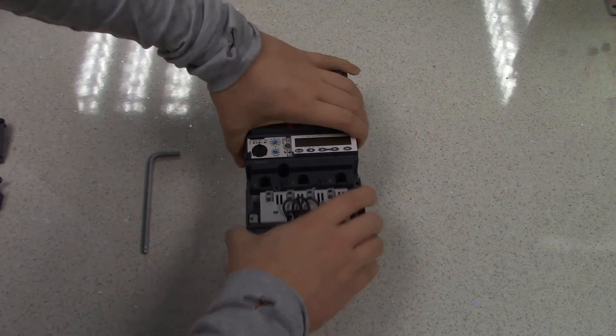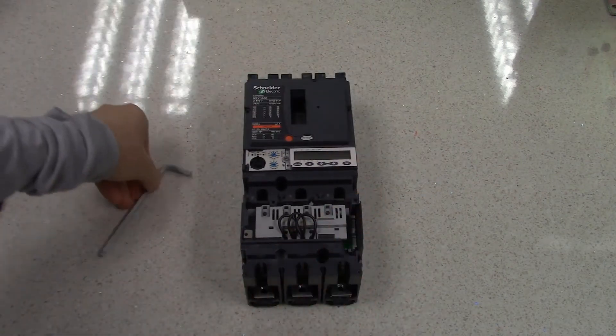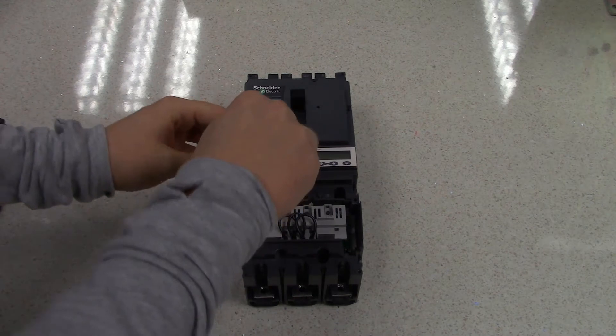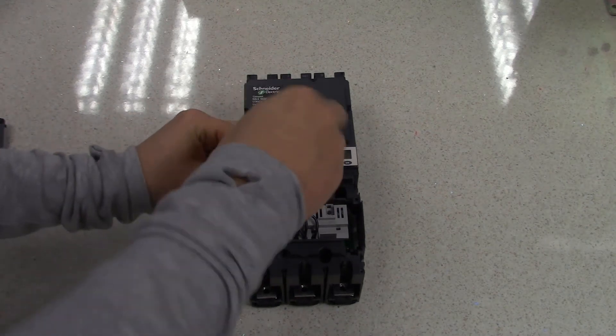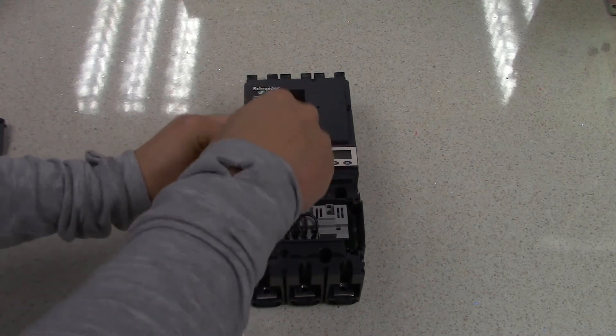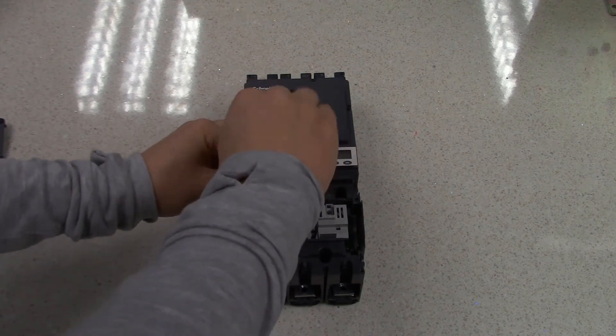Now we simply slot the two devices together and tighten up the allen keys. To do this, you will need a 5mm allen key. As this is a 160 amp device, it needs to be tightened up to 15 Nm.